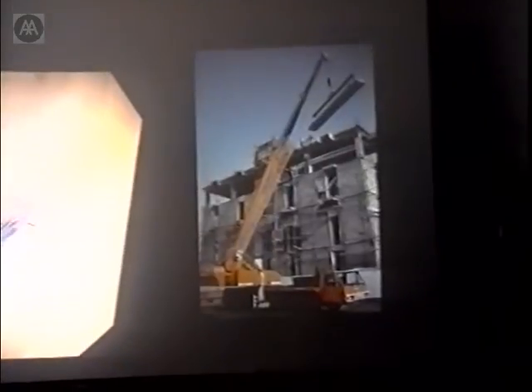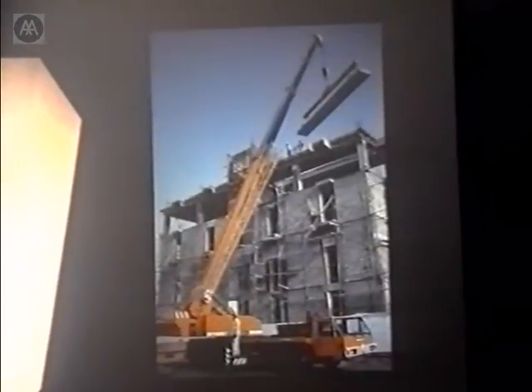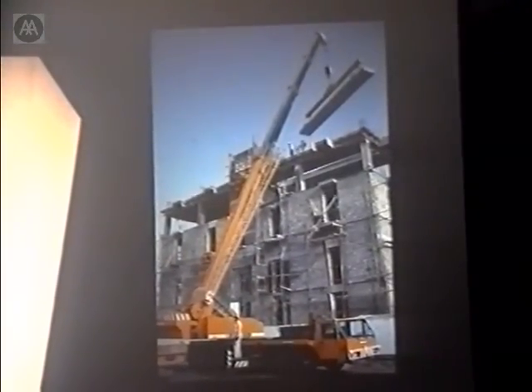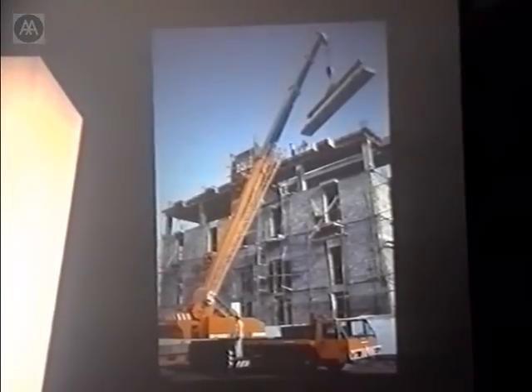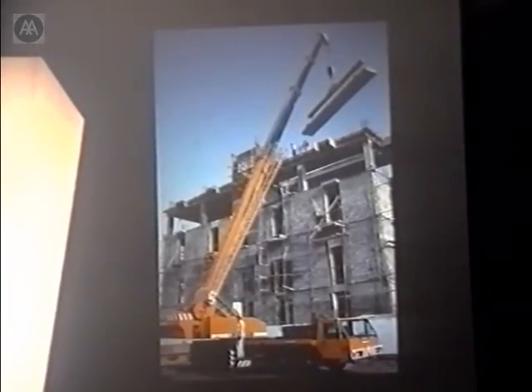This is a picture of another building, showing the hollow core slabs being installed. This one is actually in the Middle East, where even though there's not necessarily available cool air at the temperature you want, although it's a lot cooler at night than during the day, you can deliberately cool it with a chilling plant, and it reduces the size of the chilled plant by a factor of about 8.